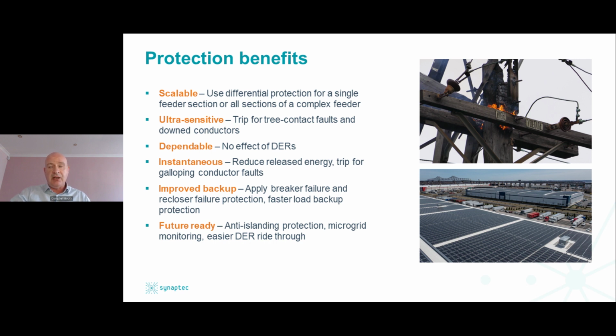If you have measurements from a lot of places, then that opens up opportunities to be a bit more sophisticated about your backup protection, rather than maybe just using time and current graded systems. If you have this differential type of measurement and distributed measurements in general, you can apply some logic and algorithms to actually identify perhaps when a breaker has failed and trip those adjacent breakers more quickly, using a kind of circuit breaker fail type logic that you might find in a transmission substation across a network in a distribution system. And faster clearance may be good if you've got more sensitive loads and of course more distributed energy resources in our future systems.